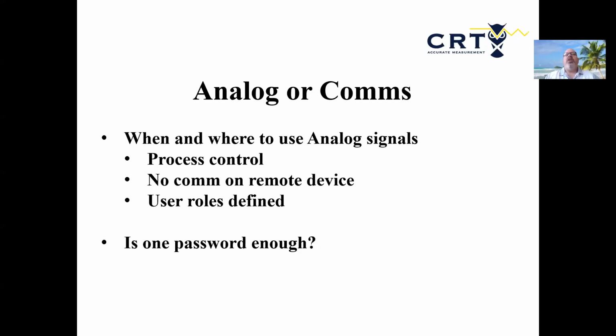If it's HART or Modbus, I can just pull the process value directly. I don't have to worry about scaling, because I'm just reading a register inside the transmitter—if it says 50 degrees and I pull that register and it says 50, I don't care if the analog signal is off a little; I know it's 50 degrees. I don't have to worry about scaling on my side. The downside is if we lose communications, you're not updating your process value.